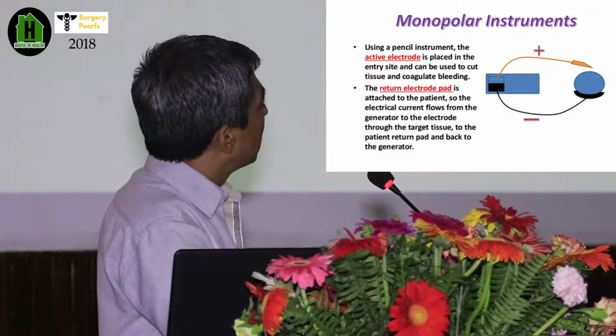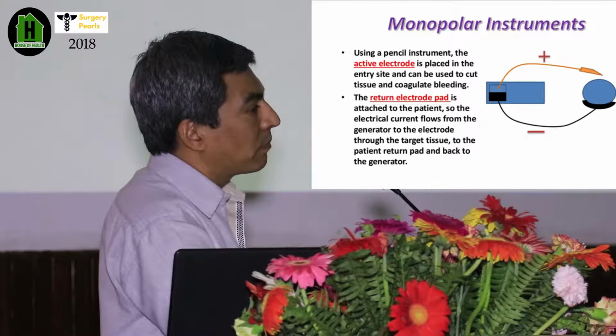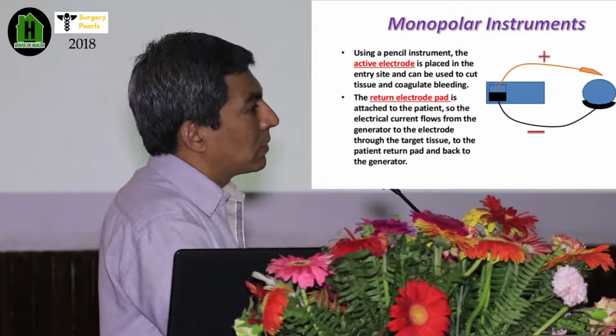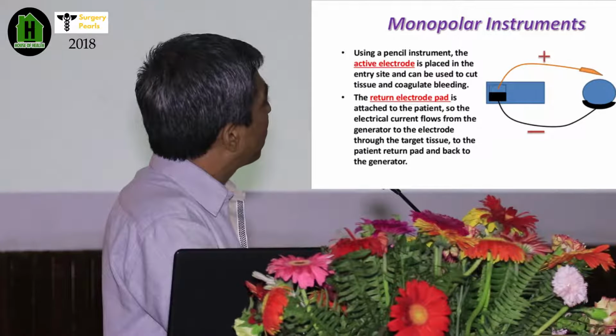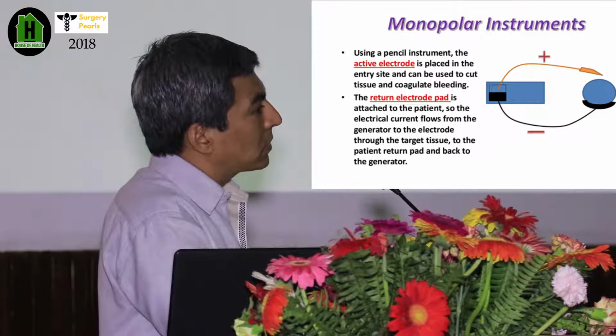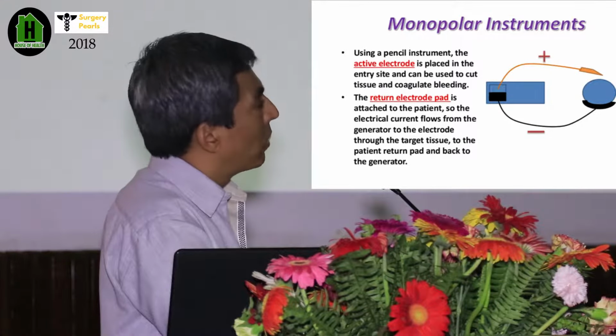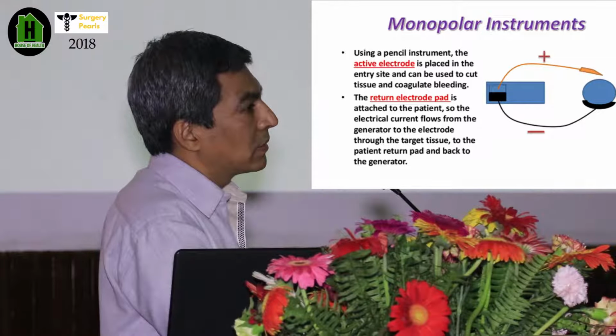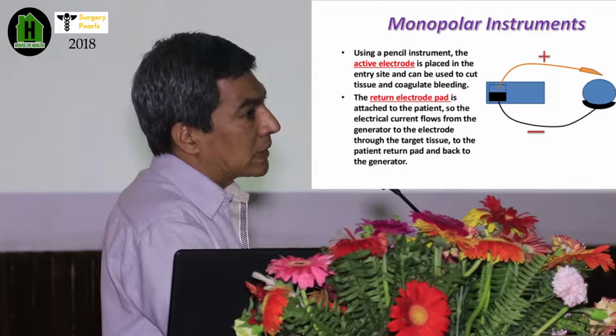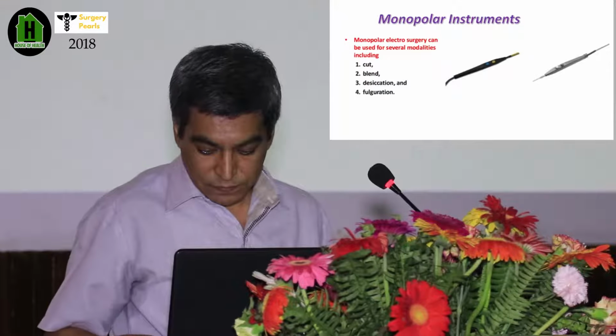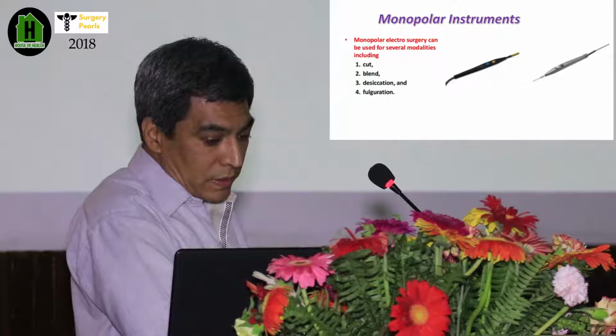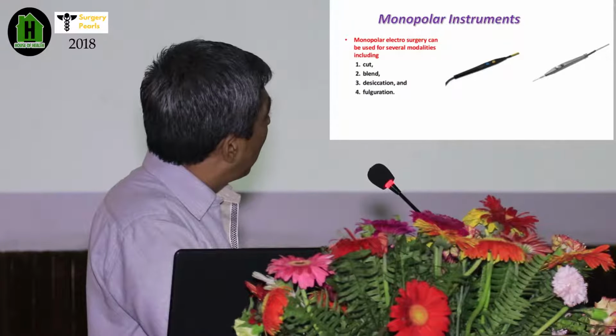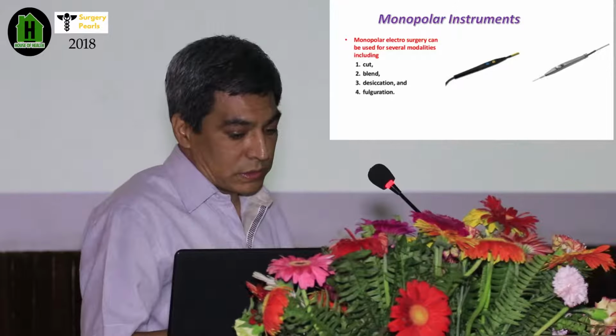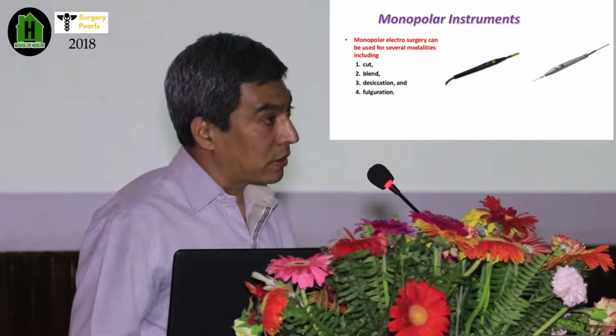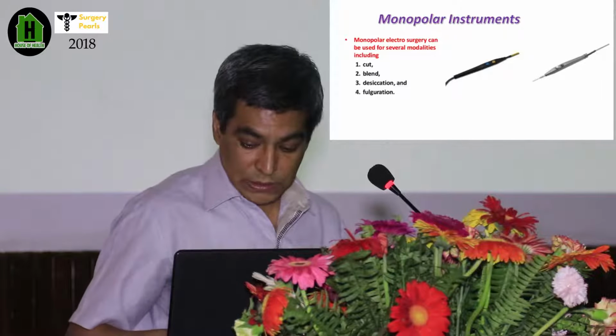If you have any leakage here, the electrons will not necessarily come back through this passive electrode. They might leak the other way around, giving unwanted effects. So you have to be careful about this. Most of us do not care about the passive electrode. We always think the active electrode is the main thing, but the passive one is equally important. So these are the monopolar hand instruments. They can produce different types of tissue effect like cut or blend, desiccation and fulguration.